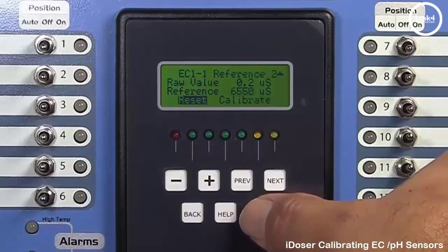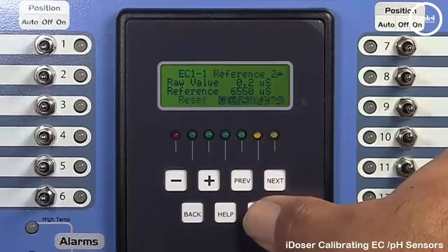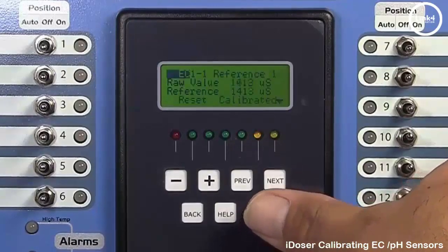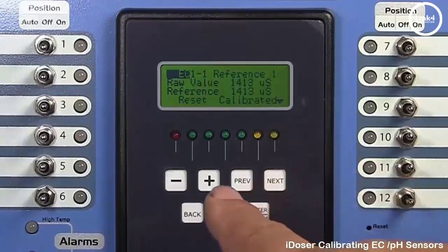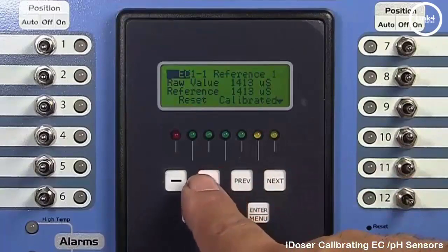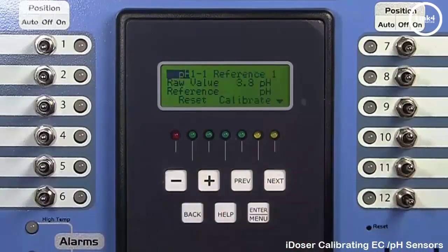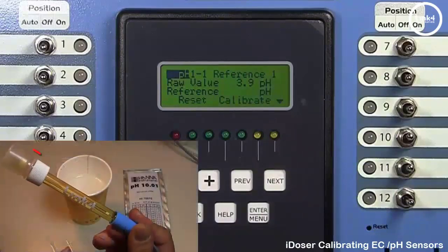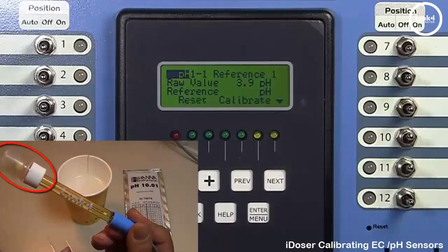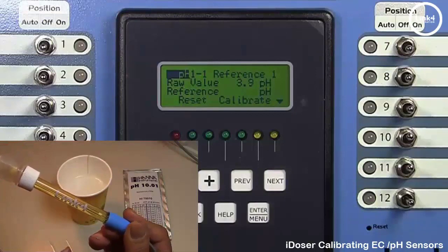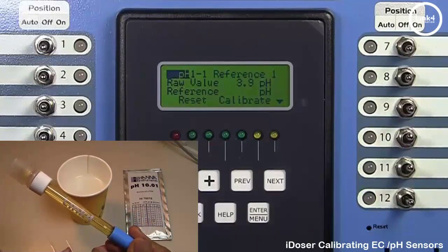And scrolling through the Reference 2 screen, which is utilized for a 2-point calibration application, just keep on going till you get back to Reference 1. And then we want to go ahead and hit plus so that we can do our pH calibration. Now the pH probe has 4 pH solution with it right out of the box. And with this probe, we want to do a 2-point calibration.